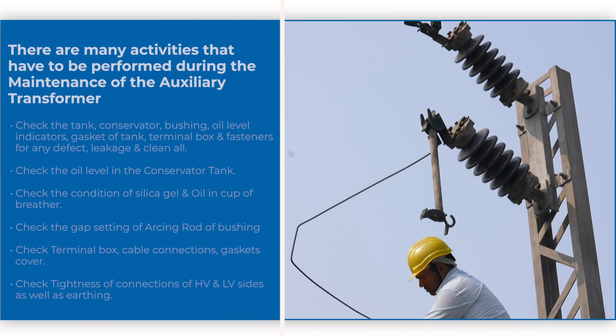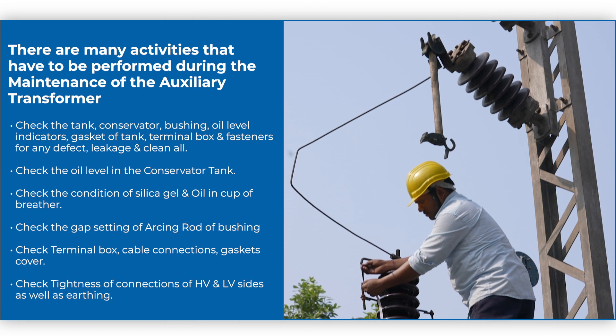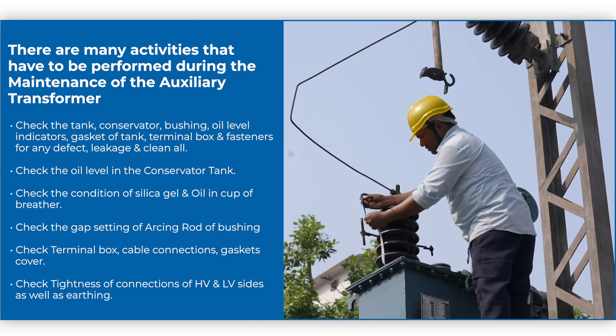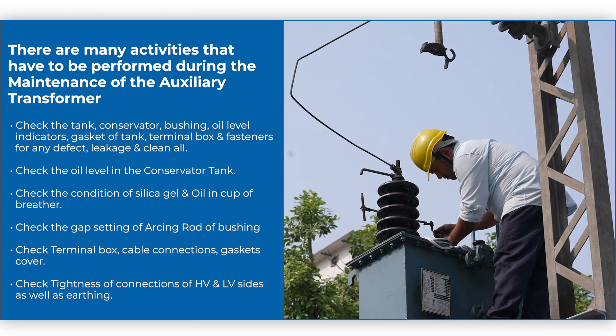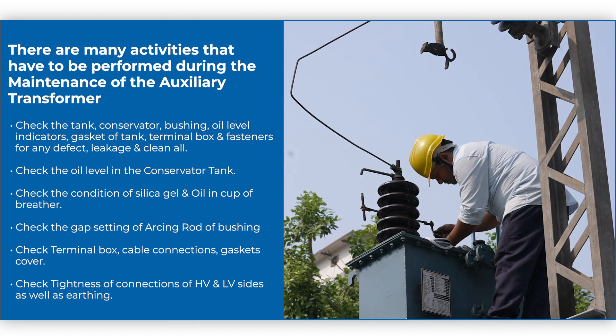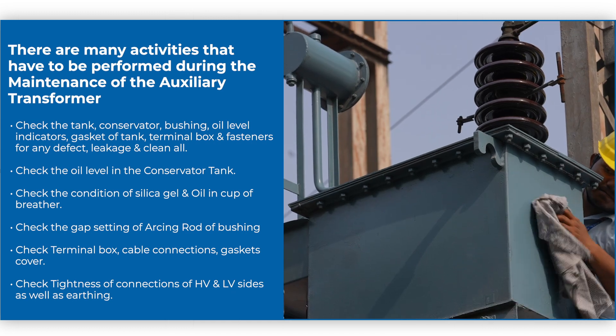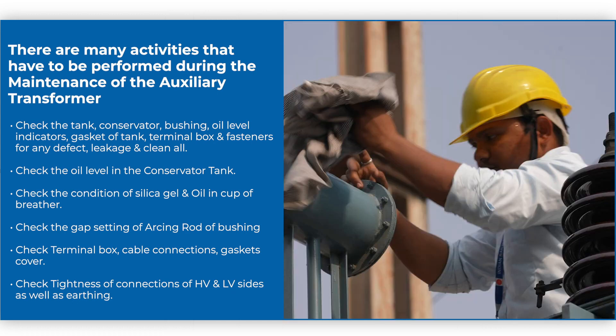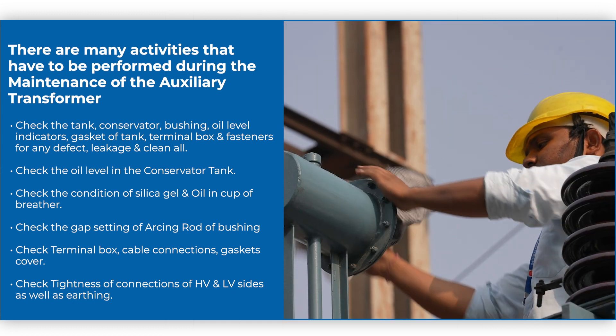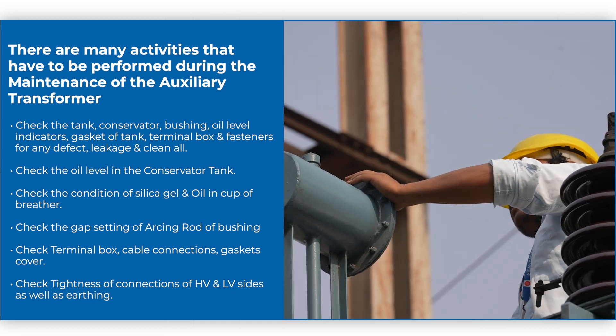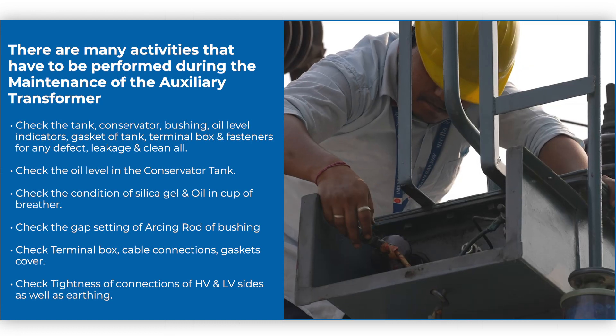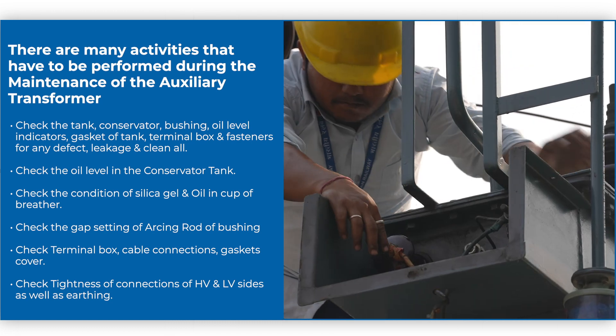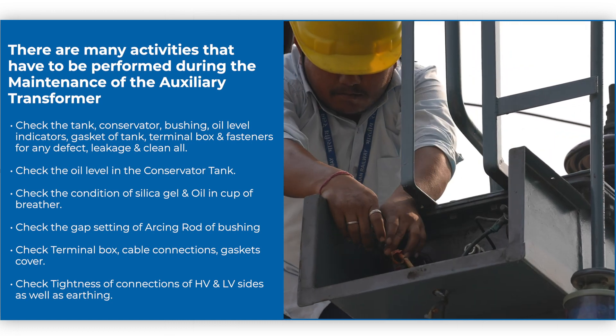There are many activities to be performed during the maintenance of the auxiliary transformer. Check the tank, conservator, bushing, oil level indicators, gasket of tank, terminal box, and fasteners for any defect, leakage, and clean all.